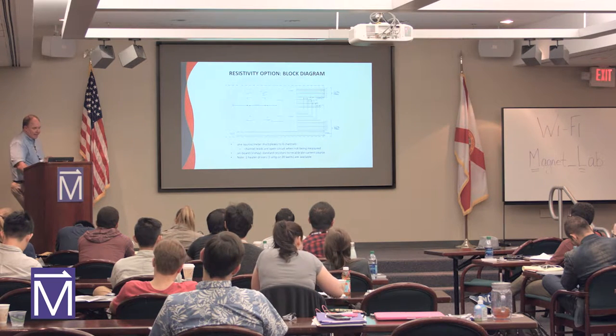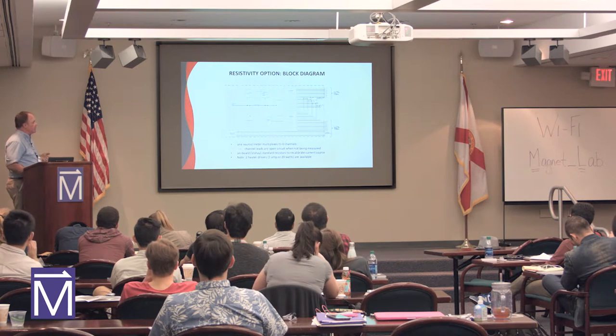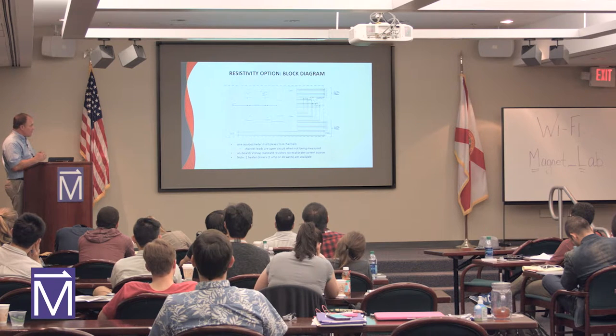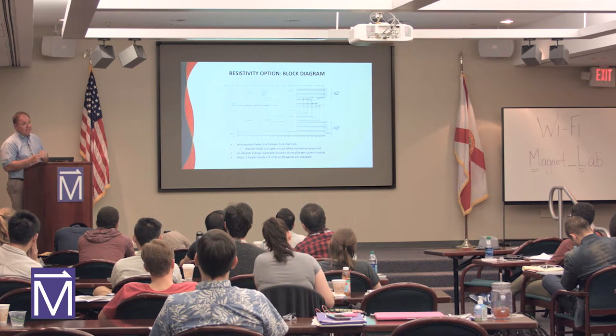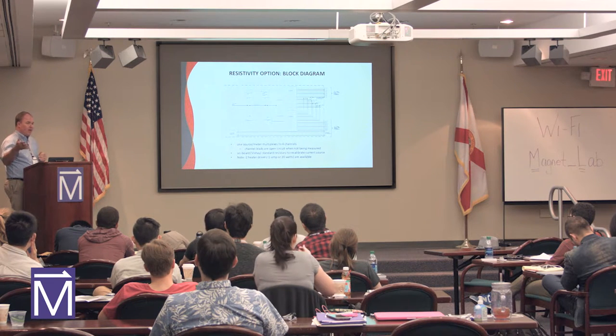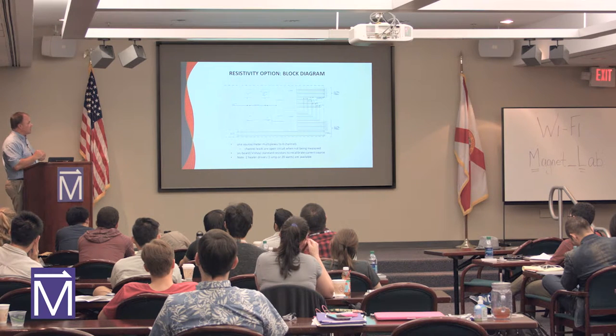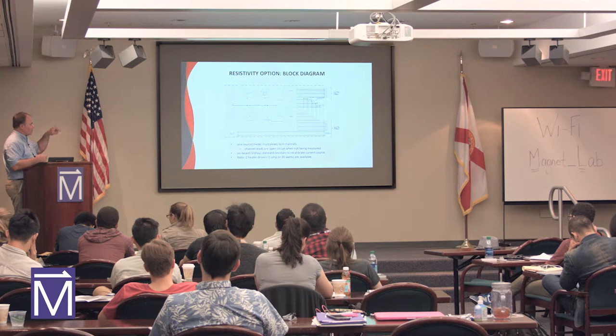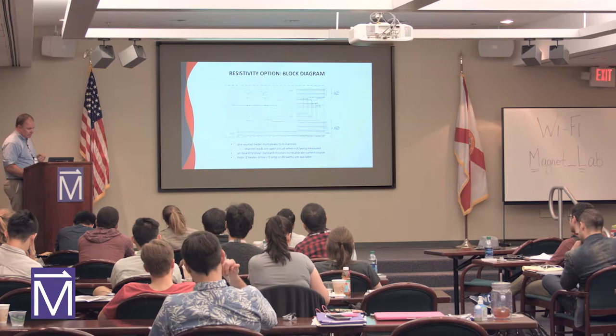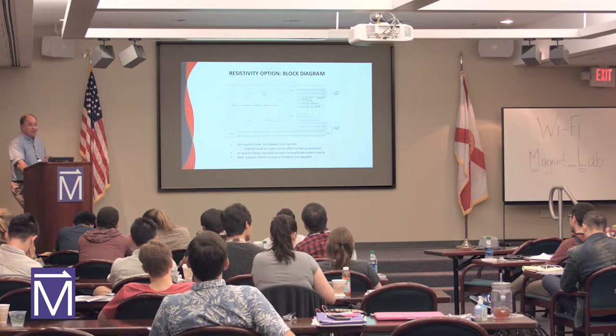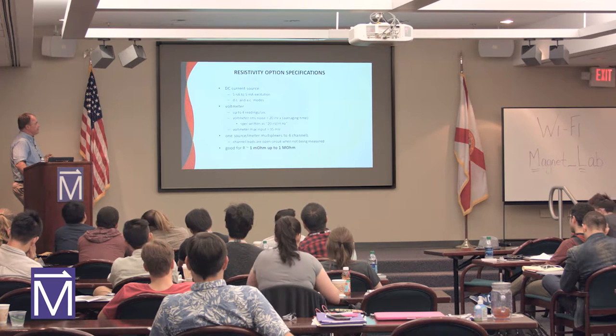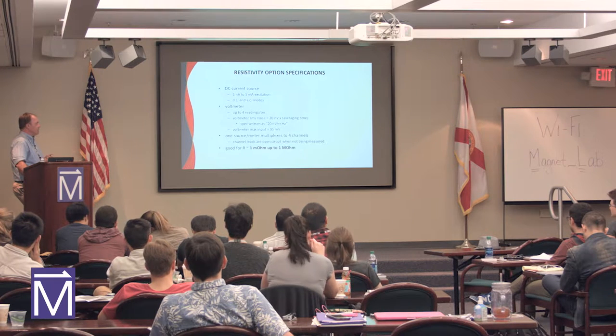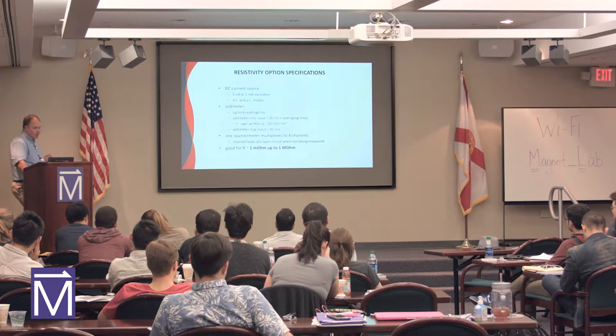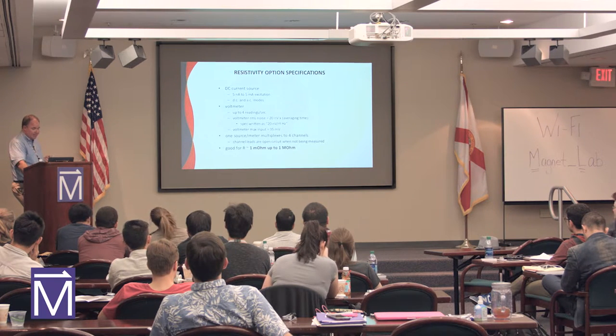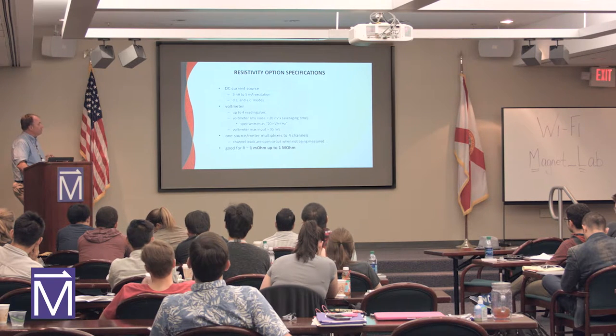Here's a block diagram of the resistivity option. We use a little multiplexer inside, and the leads are open circuit when they're not being measured. There are standard resistors inside the system so that we know the exact resistance, so we can know the current source value. And there are a couple of heaters in there, so this whole circuitry drives the heaters as well. So we've got a 1 amp or 20 watt circuit to put the heaters on to heat the sample space up. 5 nanoamp to 5 milliamp excitation, 4 readings a second. The portion of the slide to talk about is that 1 milliohm to 1 megaohm is the good sweet spot for that measurement.